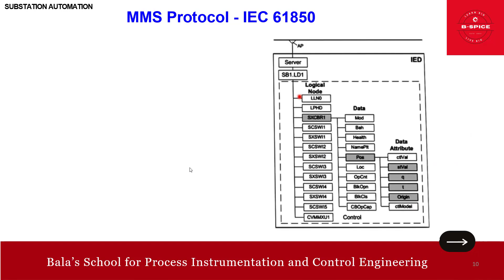So this is what I told. IEC 61850 is an object-oriented standard. So here, just listen, friends. This is what's happening here. Each physical device contains one or several logical devices. So this is your physical device, this is your logical node. As you can see here, each logical device contains logical nodes inside it. So on each logical device, you have one or several logical nodes. So physical device, then logical device, then you have a logical node.